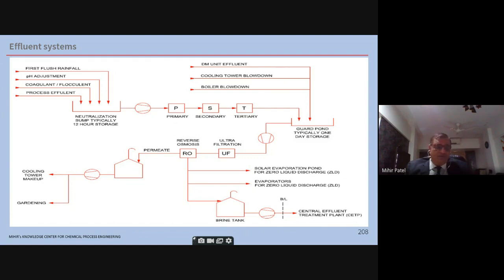Now, suppose you have a permission from the pollution board that you can send out this effluent, then fine. This effluent can be diverted directly out if it is meeting the pollution board limits, or if it is a ZLD plant, so zero liquid discharge. Now the pollution boards are insisting that new processes always have a ZLD. So if you have zero liquid discharge, then you have to pump it back to the ultrafiltration, to a reverse osmosis, and recover as much water. Then the brine of the RO can be sent for evaporators. So MED, multi-effect evaporators, are kept here. And finally, then the zero liquid discharge occurs. It's only the inert solids that are taken for inert landfill. And the permeate, which is good quality water, is recycled for cooling tower makeup or gardening.